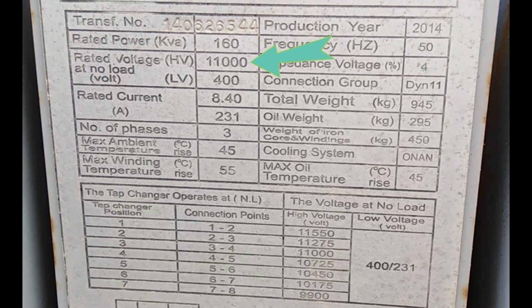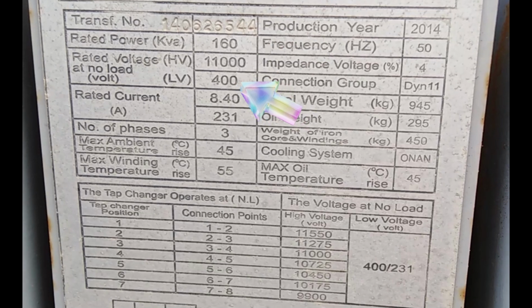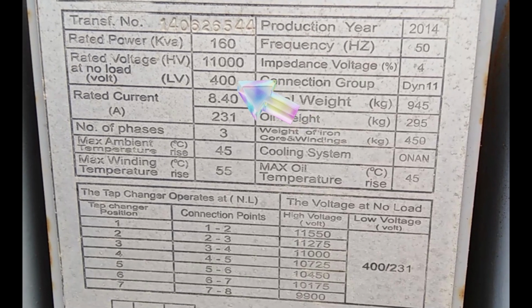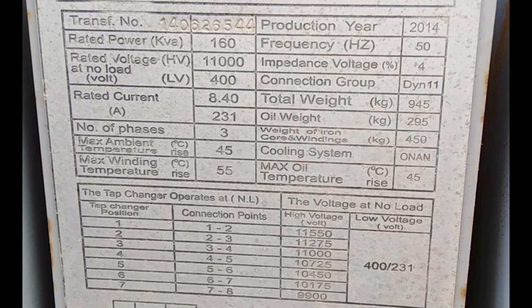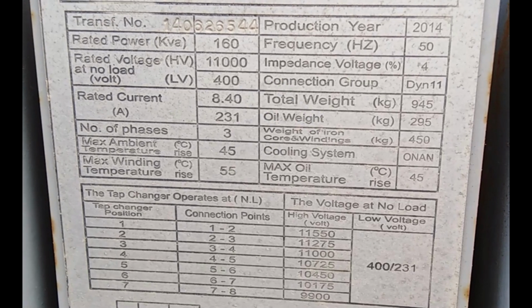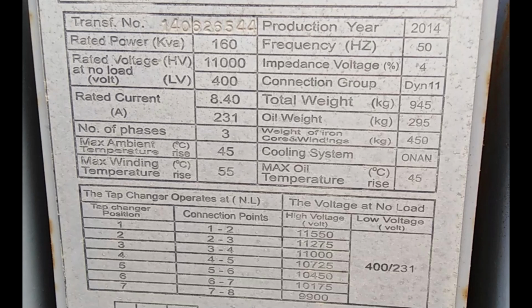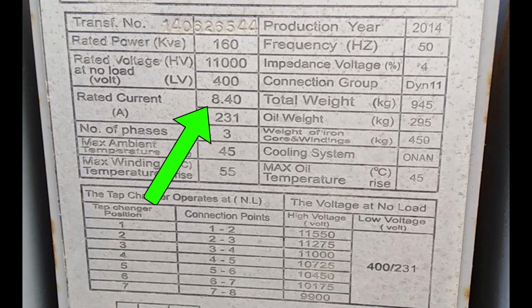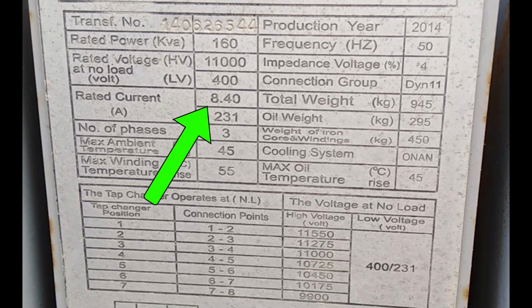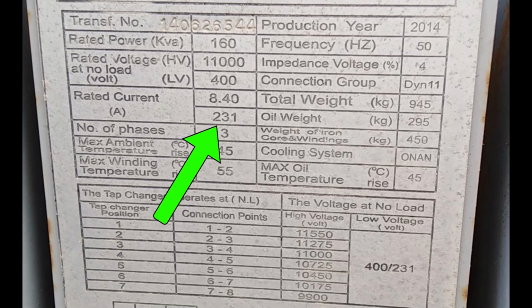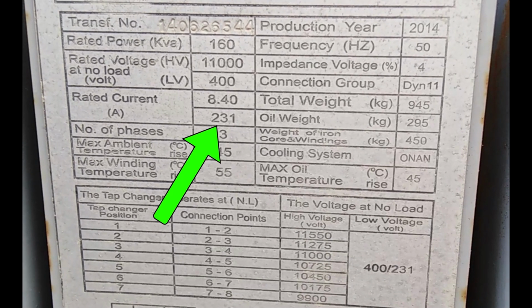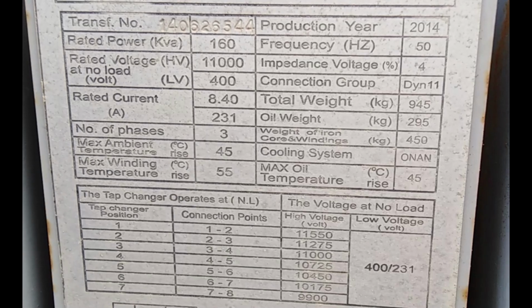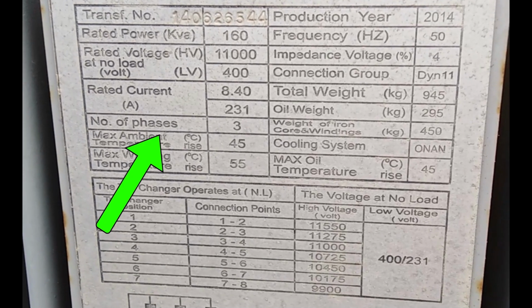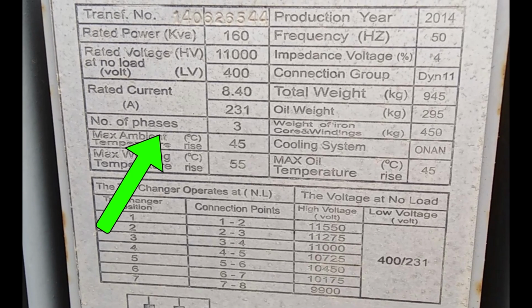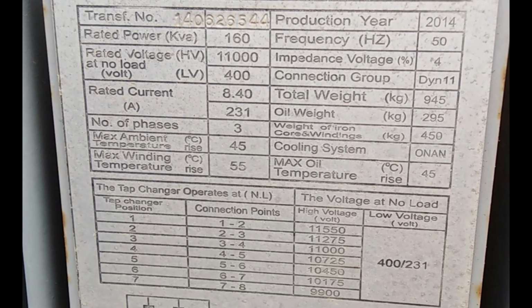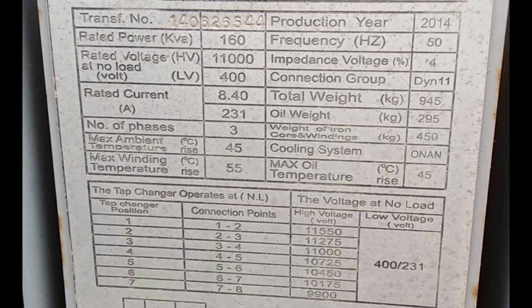We've got a high side voltage of 11,000 volts and a low side voltage of 400 volts. This tells us the voltage levels the transformer can handle and step down from and to, making it a key player in ensuring the electricity is at the right level for our homes and businesses. Rated currents next, 8.4 amps for the high voltage side and a whopping 231 amps for the low voltage side. This info helps in designing the system's conductors and ensuring safety and efficiency. With the number of phases being 3, it confirms that this transformer is perfect for 3-phase power systems, which are common in industrial and commercial settings for their efficiency and power consistency.